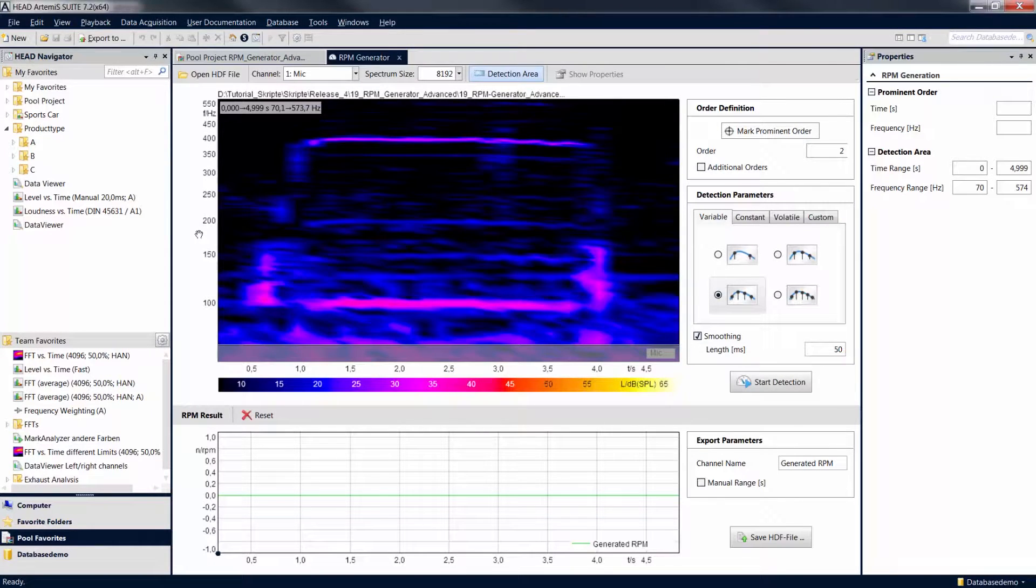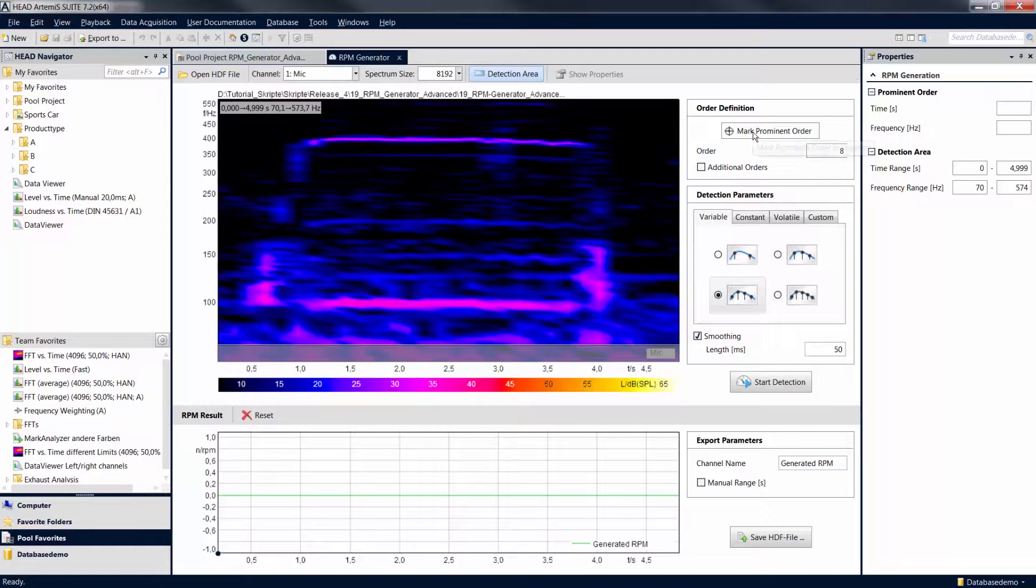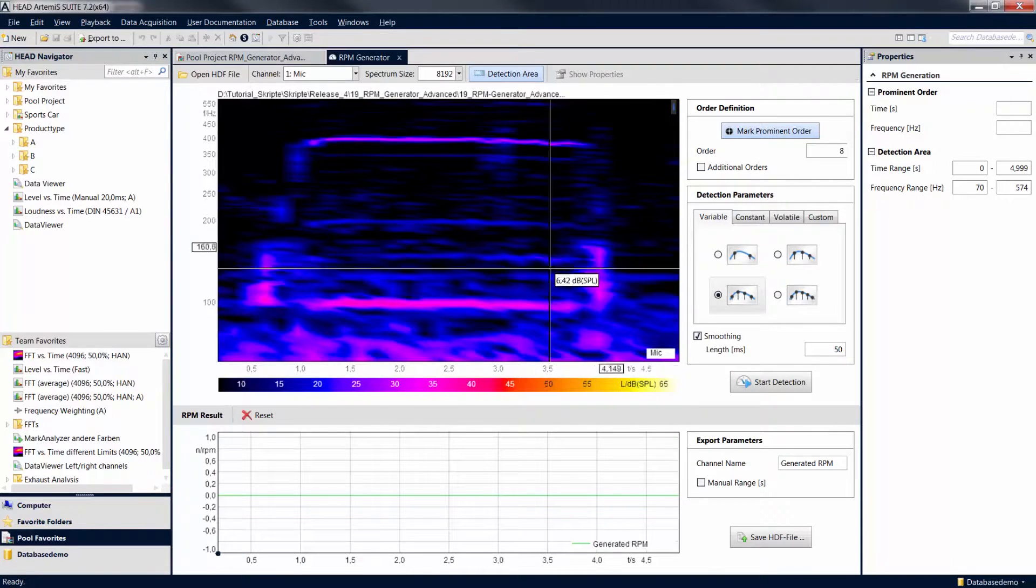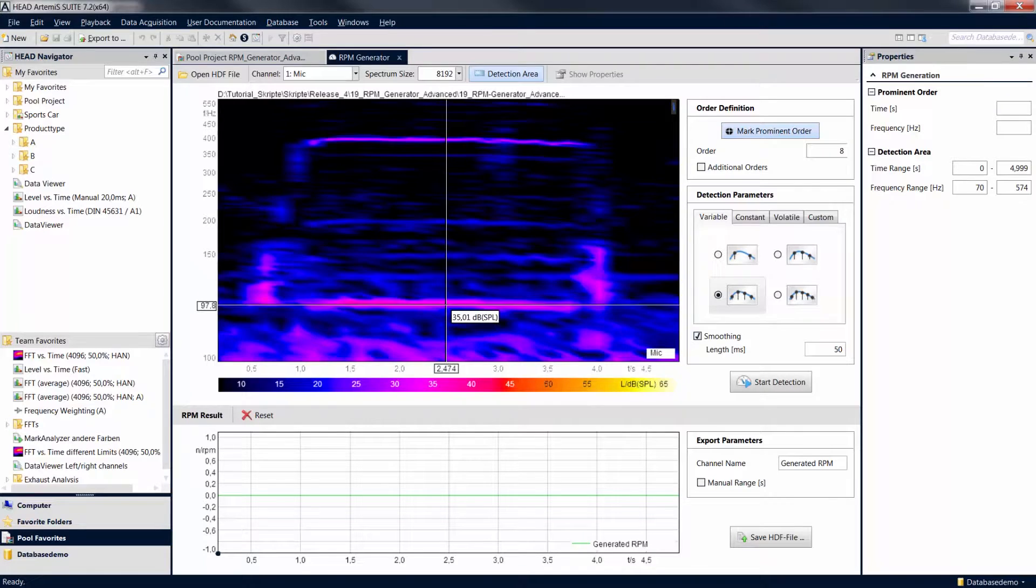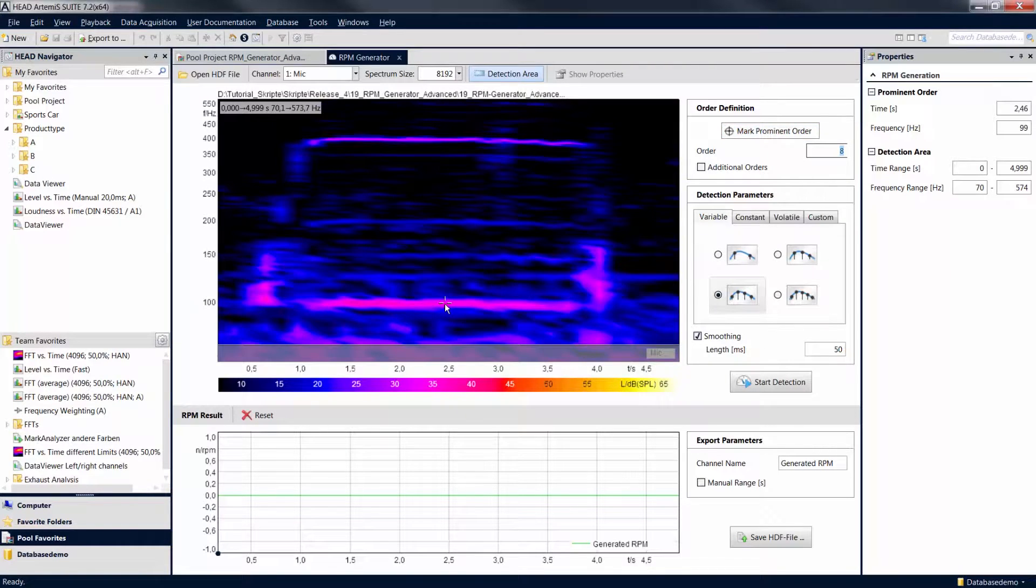In this example we want to determine the revolution speed curve of an electric motor. Go to the order field and enter the number of an order that is clearly visible in the signal representation. Then click on Mark Prominent Order. In this case, the low frequency tonal component is the 8th order.